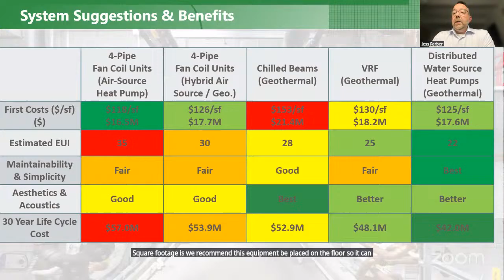So for those units, one reason we have allocated square footage is we recommend this equipment be placed on the floor so it can be serviced. We want that unit to be in a mechanical closet that you can get to, accessible from the corridor, not having to get into the educational space to take care of it. Whereas a fan coil unit is going to be above a ceiling, it gets a little more difficult to take care of because we're not going to put them in the classrooms since those are noisy. Used to be you put unit ventilators and fan coils on the floor, we just don't do that anymore for acoustics in the classroom learning environment. So those would be above a ceiling.